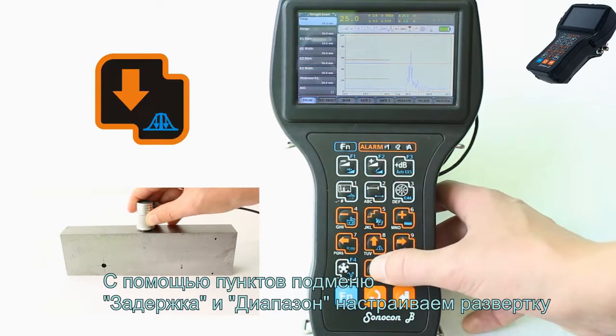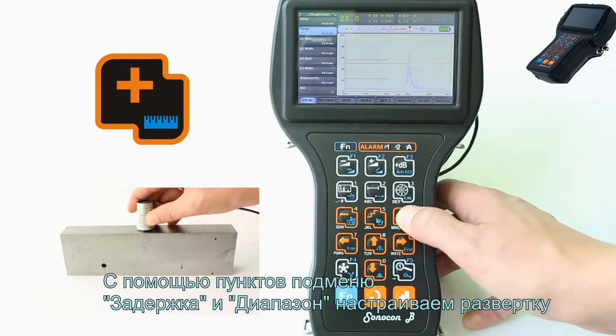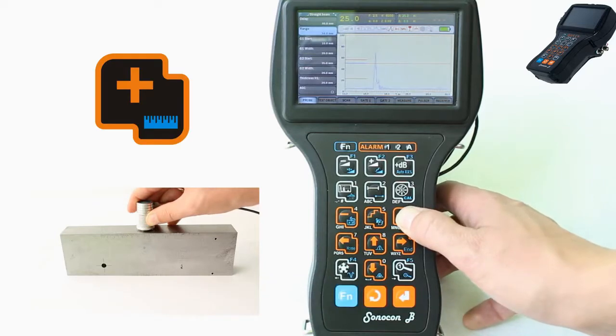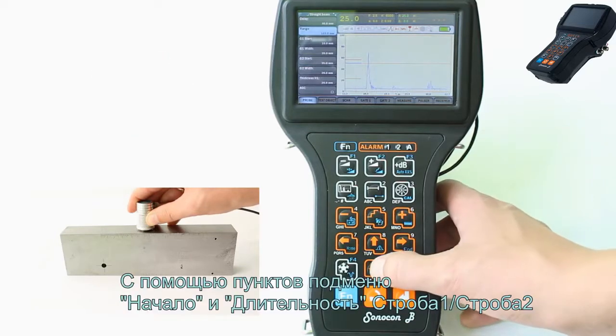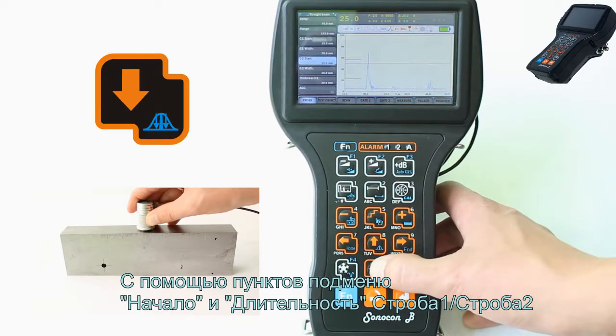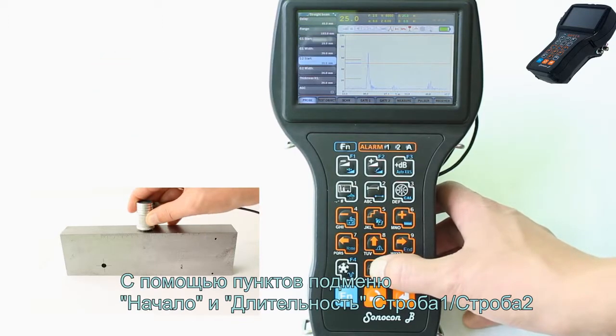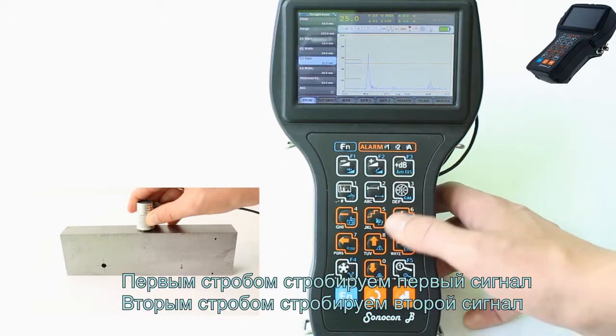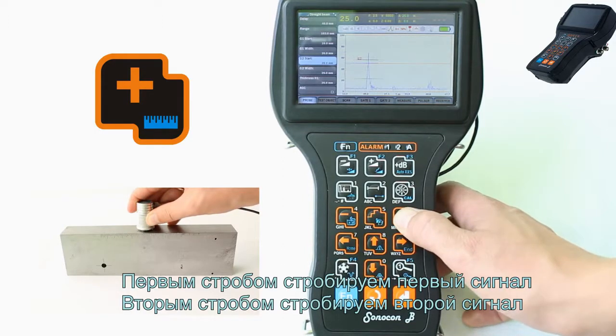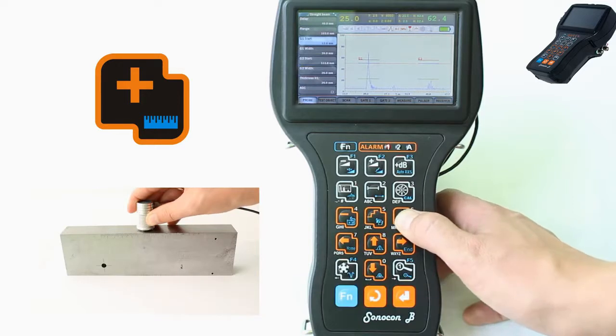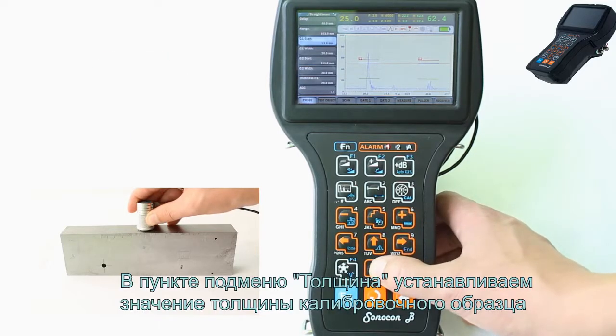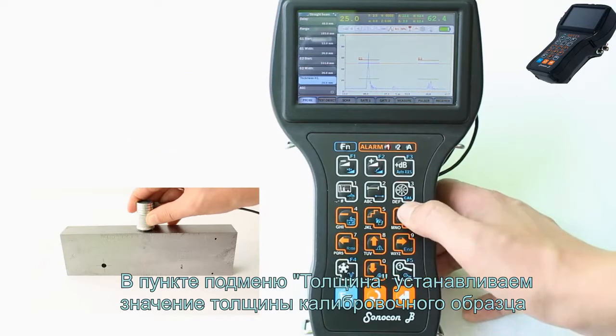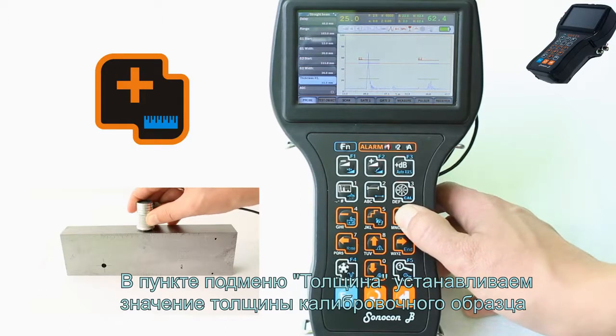We can set up the scan using the submenu items delay and range, as well as start and width for gate 1 or gate 2 respectively. The first signal is gated by the first gate, the second signal is gated by the second gate. With the submenu item thickness, we can set up the calibration block thickness.